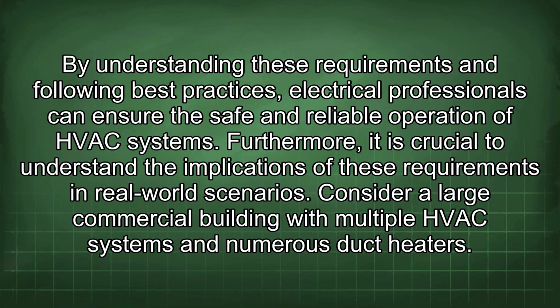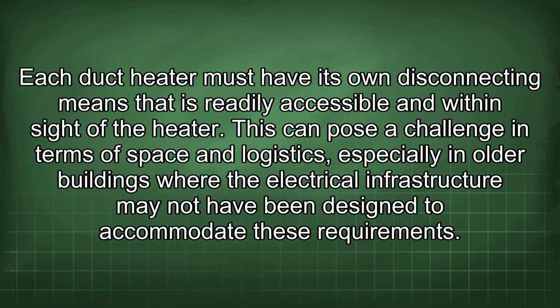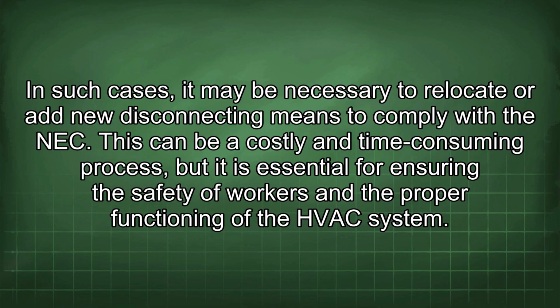Consider a large commercial building with multiple HVAC systems and numerous duct heaters. Each duct heater must have its own disconnecting means that is readily accessible and within sight of the heater. This can pose a challenge in terms of space and logistics, especially in older buildings where the electrical infrastructure may not have been designed to accommodate these requirements. In such cases, it may be necessary to relocate or add new disconnecting means to comply with the NEC. This can be a costly and time-consuming process, but it is essential for ensuring the safety of workers and the proper functioning of the HVAC system.